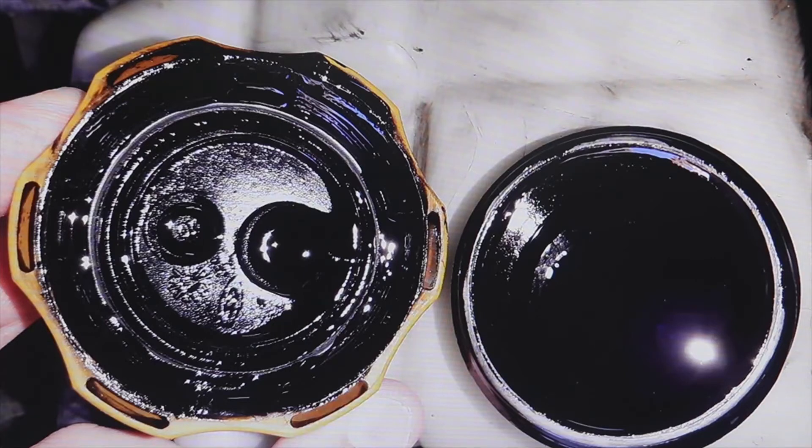How do we check it? In this case it has been simple. Check how the expansion tank looks inside. Here we have emptied the oil pan — you have to remove all the oil — and there was barely any water, very little. This is the cooler; here is how we did the test.